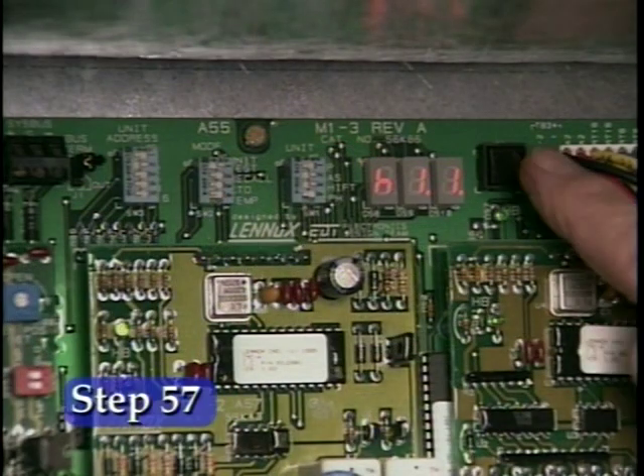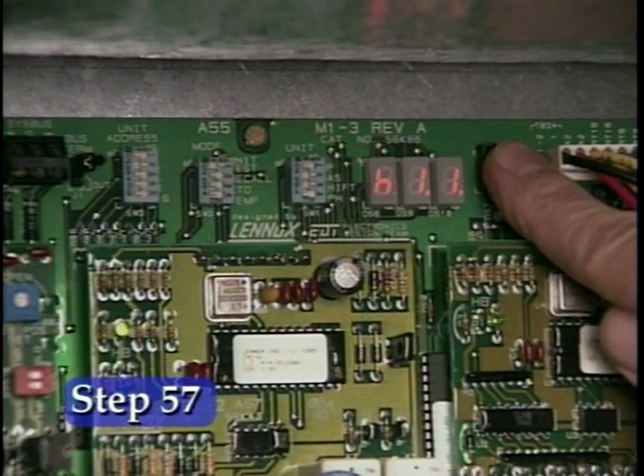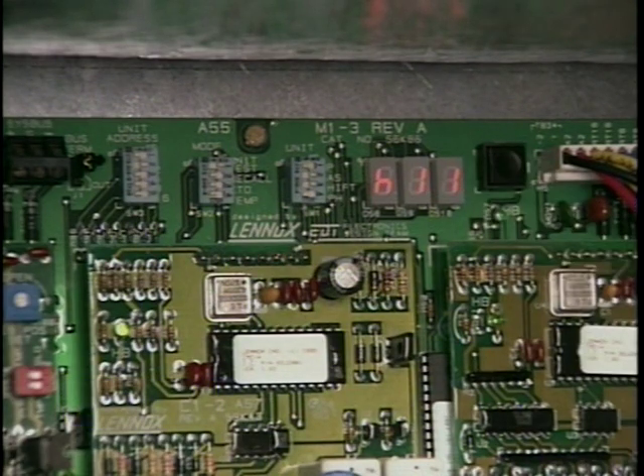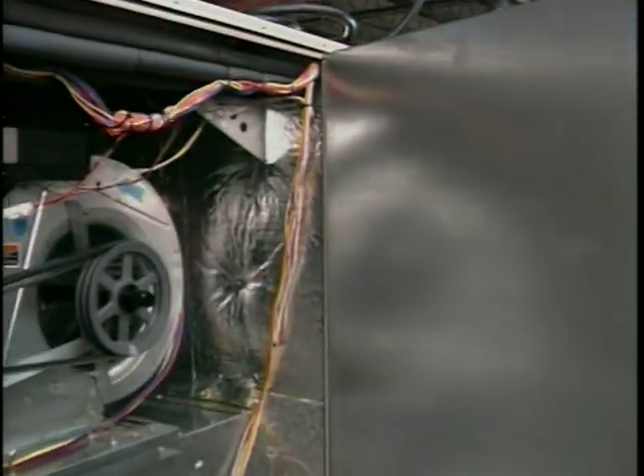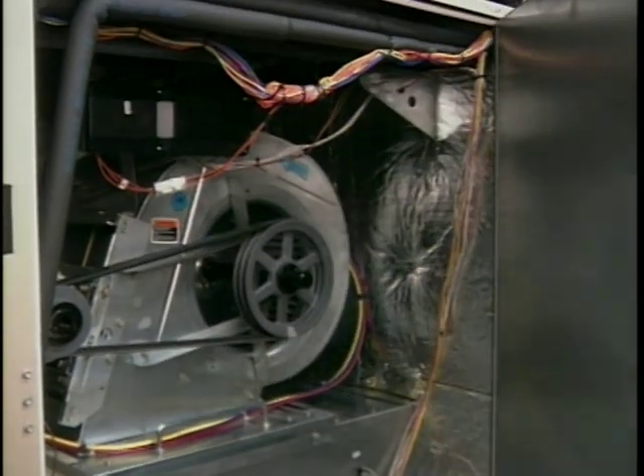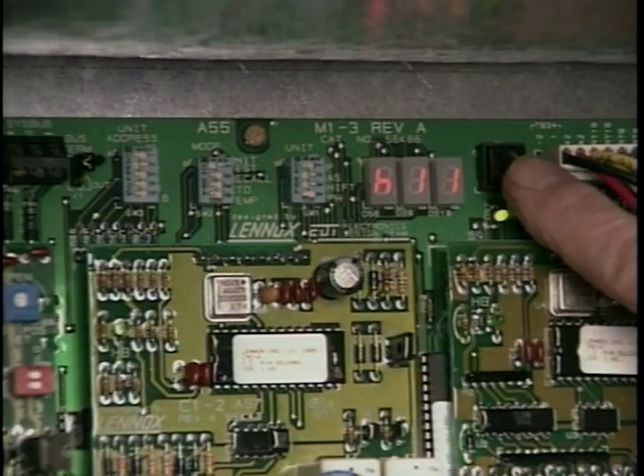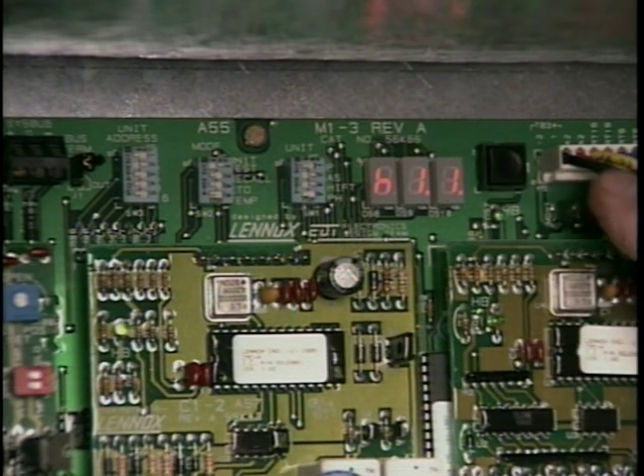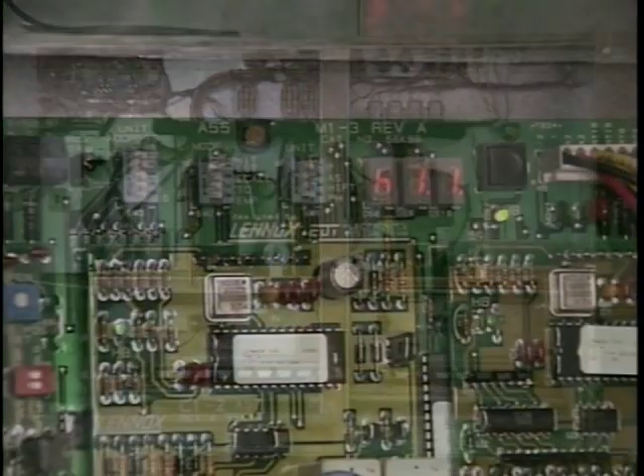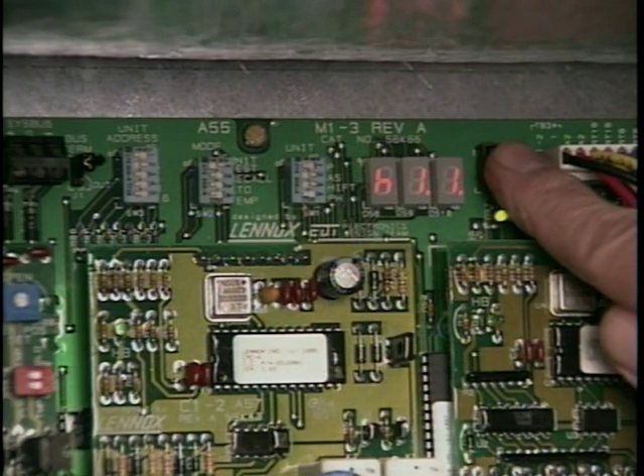Turn the gas valves and fan off by pressing the push button until the periods on the LED readout disappear. Now open the blower door and disconnect the fan power plug at the bulkhead connector. Close the blower door. Press and hold the display push button until the periods appear in the LED readout. The unit should start both stages of heat and, after a brief warm-up period, should shut off on high limit. Press and hold the display push button until the periods in the LED readout disappear.